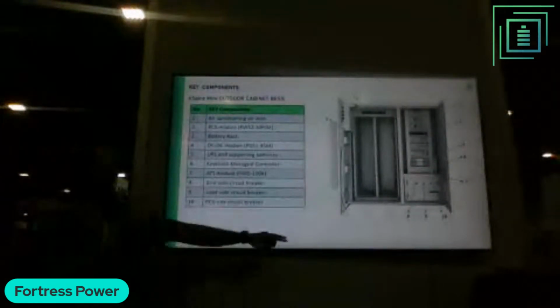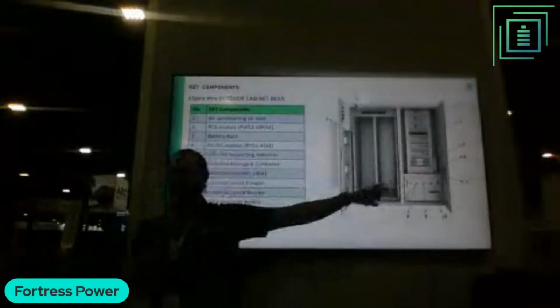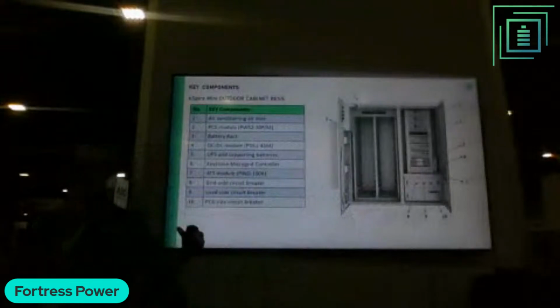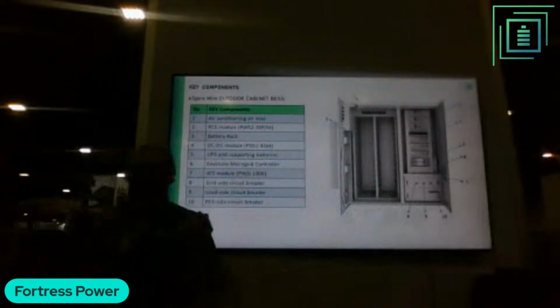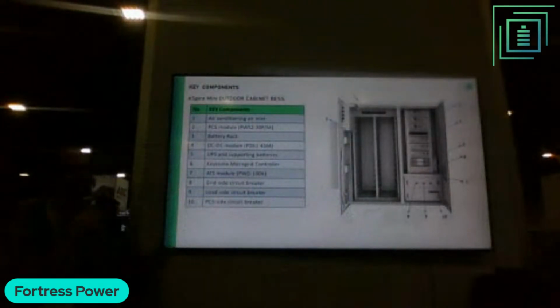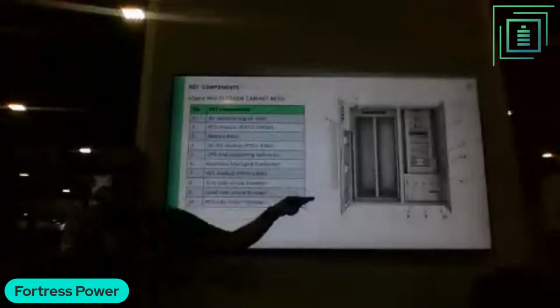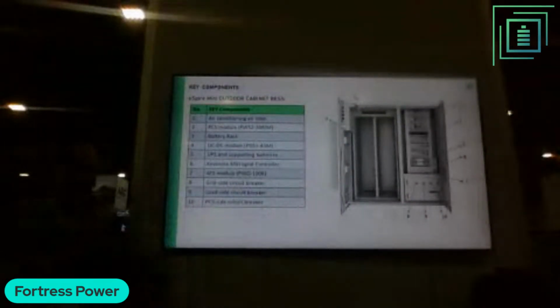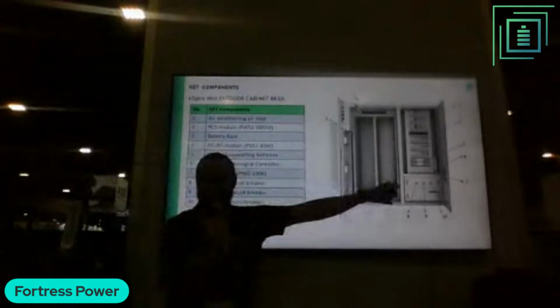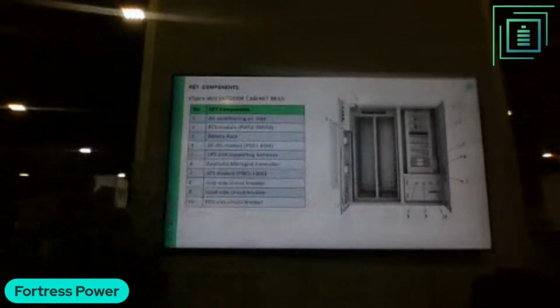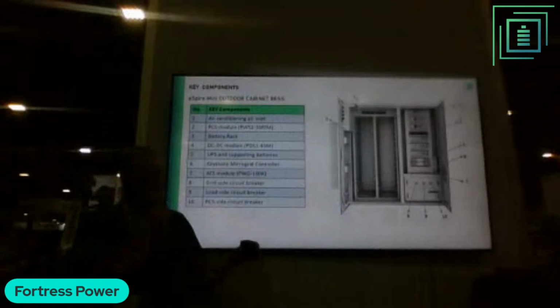In addition to this, we have UPSs built into this unit for black start. So if you need to have an islanded system and there's no grid signal to form that grid signal initially, the UPS can kickstart the battery system and allow it to form the grid. We have a static transfer switch built in here as well. So to grow from grid following to grid forming applications, you don't need an external ATS.